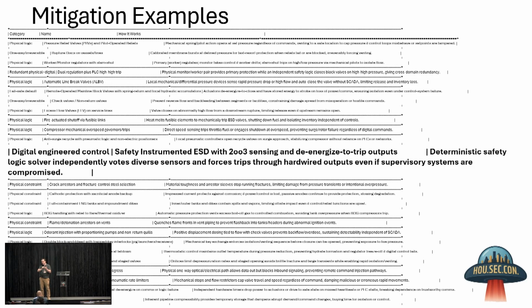If that value doesn't benefit from this resilient technique, it could cause the valve to misapply its result because of manipulation occurring in the controller or sensor being injected, if the controller doesn't have that voting mechanism applied as a response to the digital risk of communicating that signal over the network in a manner susceptible to digital technology. We can see how engineers, if they involve safety techniques or things they have control over from an algorithmic standpoint or as a physical technique, can eliminate that consequence.